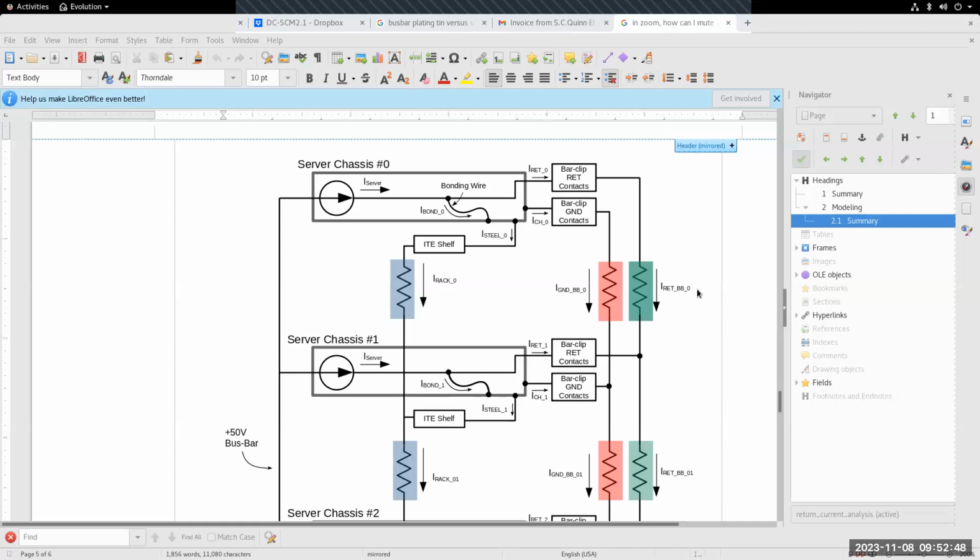It's something that we came up with a treatment for that was effective, but it was a pretty painful experience. And so coming into ORV3 and reading and learning all the different details, when I saw that the chassis ground bus bar is tin over nickel, I was like, gee whiz, has nobody in OCP run into this problem before?